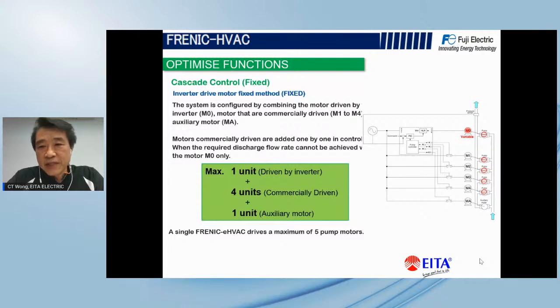For example, you have pumps M0 to M4. There will be a pressure sensor to measure and feed back to the inverter PID. Assume that one pump is 1 bar. So you have basically 5 pumps over here, so we can deliver 5 bar to the main water line. From here, for example, I start the first pump.